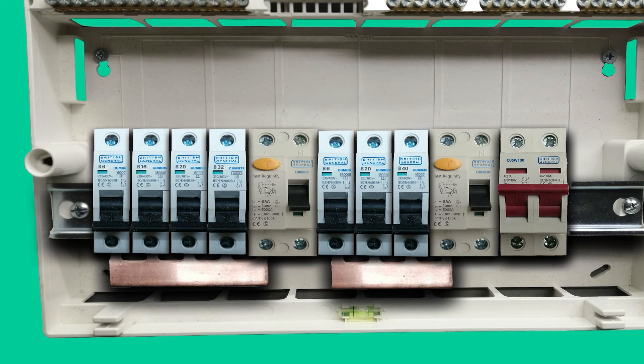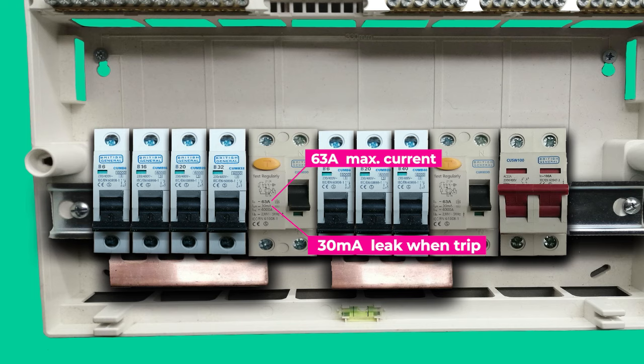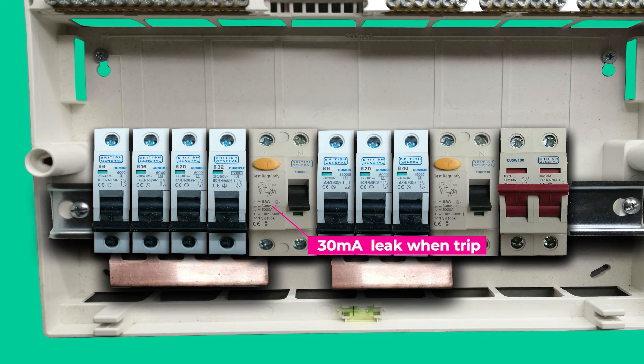There are also some numbers printed on the RCD like 63 amps. This is the maximum current for this RCD and below you can find a figure of 30 milliamps. This means that if 30 milliamps or more current leaks somewhere outside of the circuit, the RCD will trip. 30 milliamps is equal to 0.03 amp.